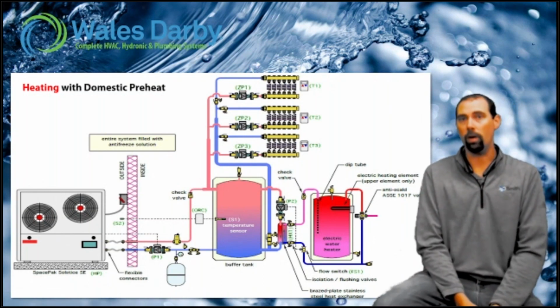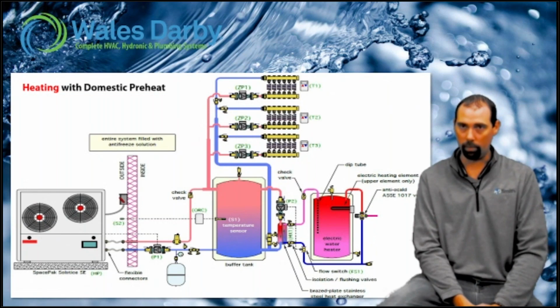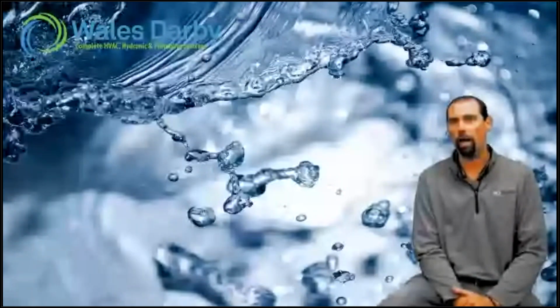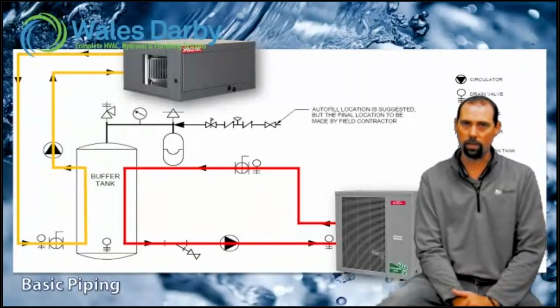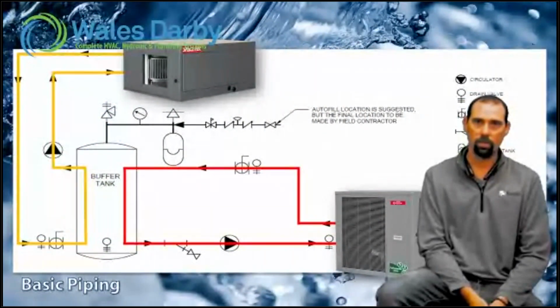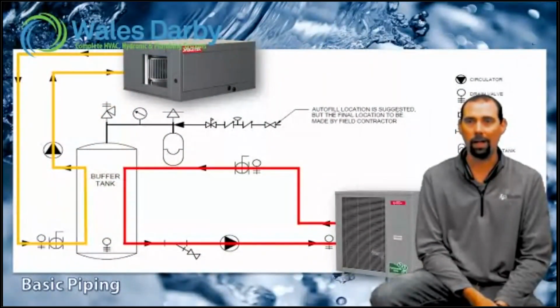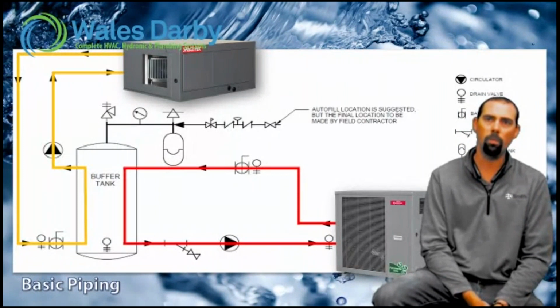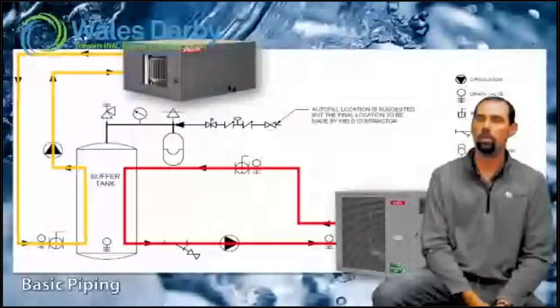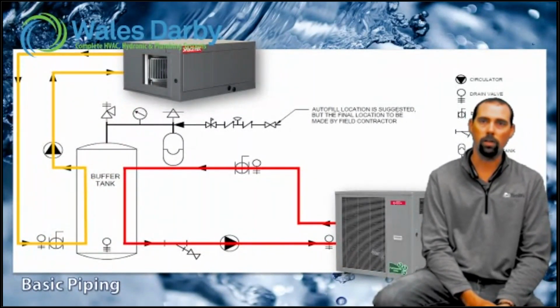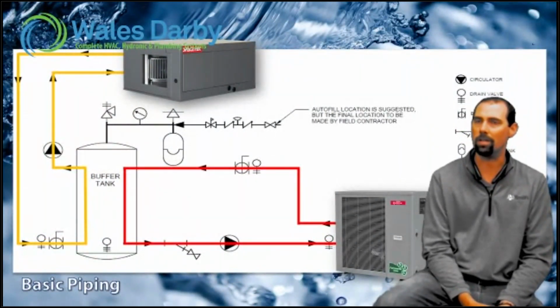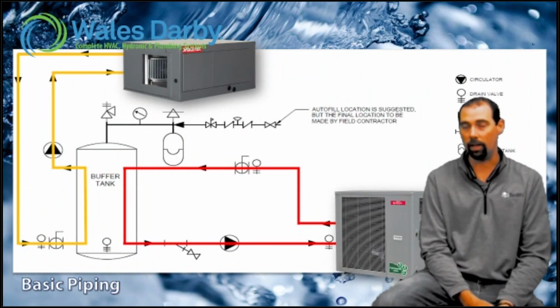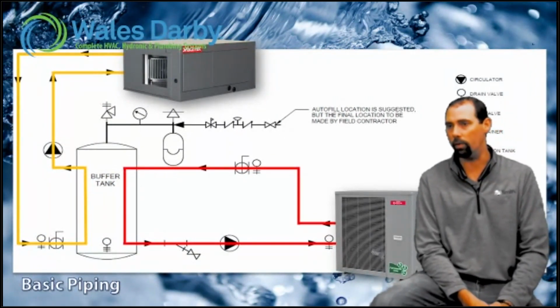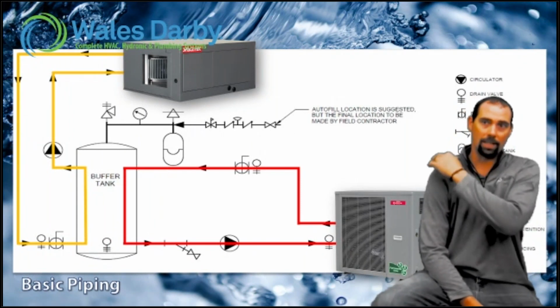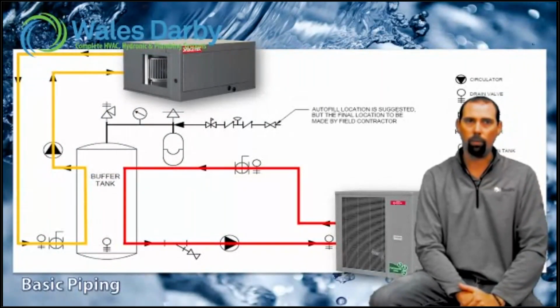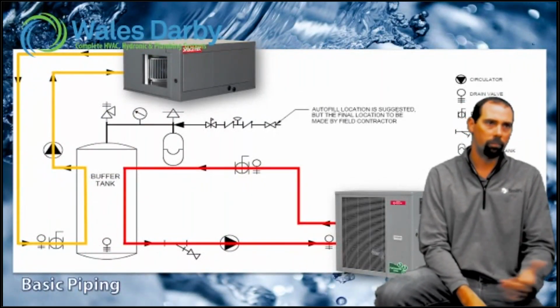Maybe it opens your eyes to something you never thought about, sparks that creativity a little bit. But this is a basic setup, and if I even go back to the first diagram, that's even simpler, right? Just a couple pipes, 2 pumps, and an air handler. If you have those setups, even in your own home, start with something like this. This would be a super efficient system electrically, and as far as cooling and comfort with the SpacePak High Velocity, you put the two together. This is something I'm really excited to look at putting into my own home, high velocity with the air to water. And again, we could incorporate a boiler into the mix, but it's still very easy.